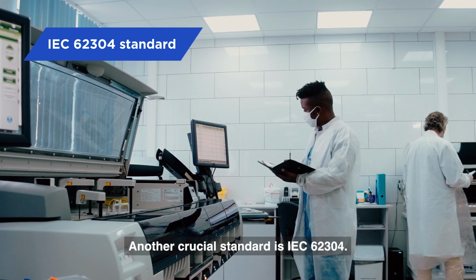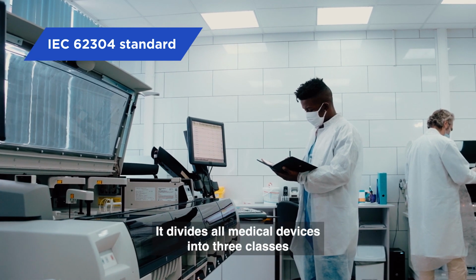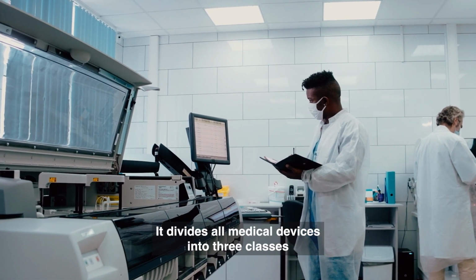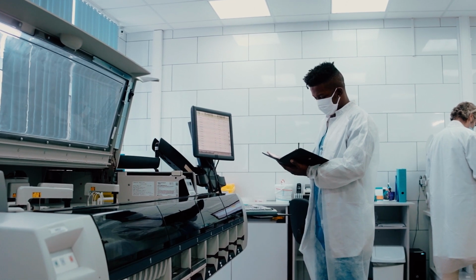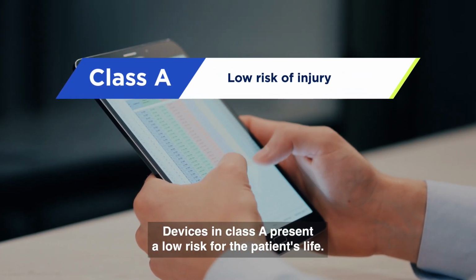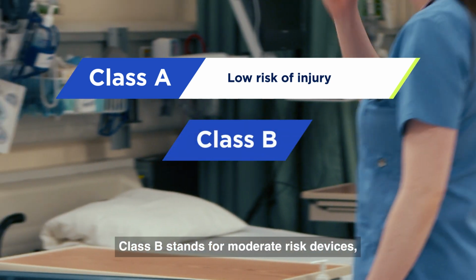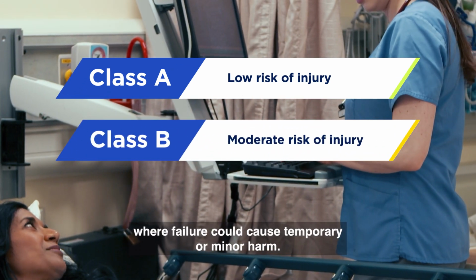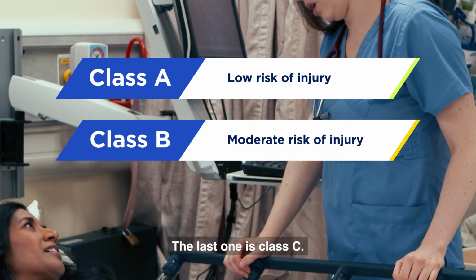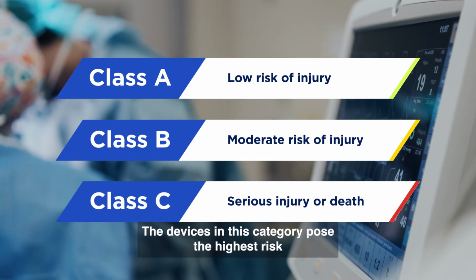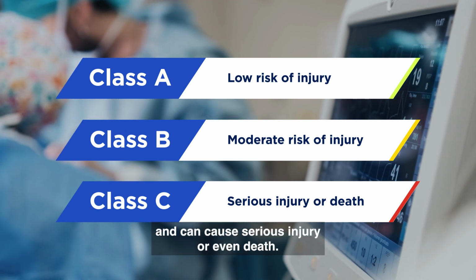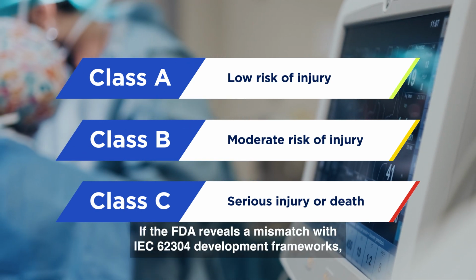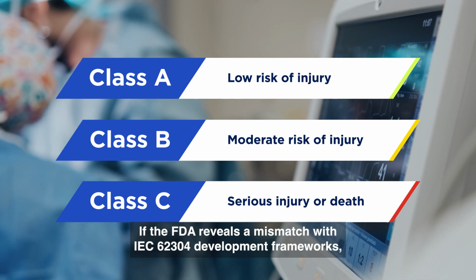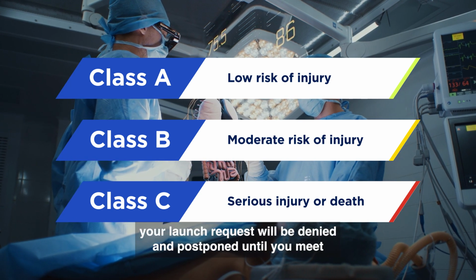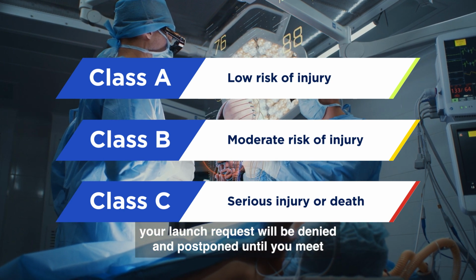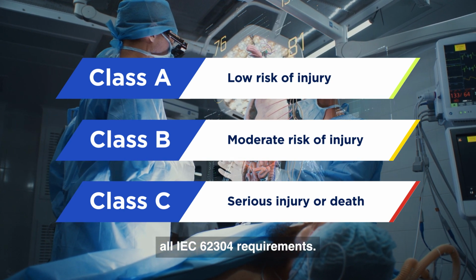Another crucial standard is IEC 62304. It divides all medical devices into 3 classes, depending on their medical intention and safety risk. Devices in Class A present a low risk for the patient's life. Class B stands for moderate risk devices, where failure could cause temporary or minor harm. The last one is Class C. The devices in this category pose the highest risk and can cause serious injury or even death. If the FDA reveals a mismatch with IEC 62304 development frameworks, your launch request will be denied and postponed until you meet all IEC 62304 requirements.